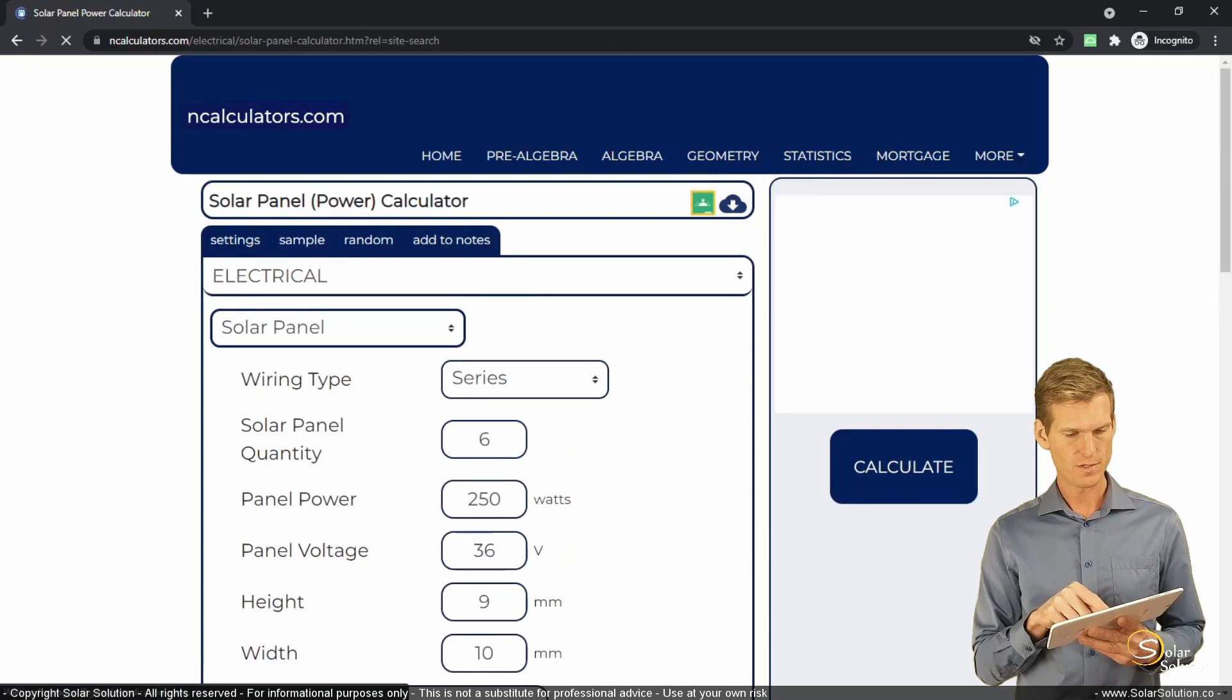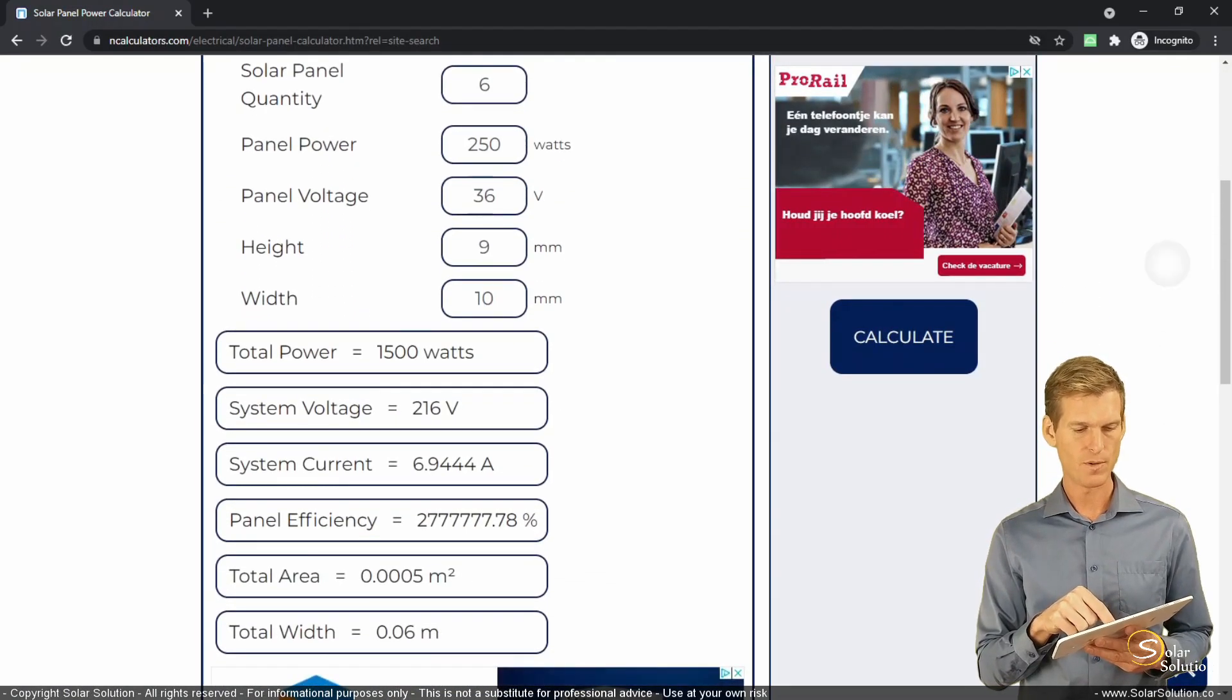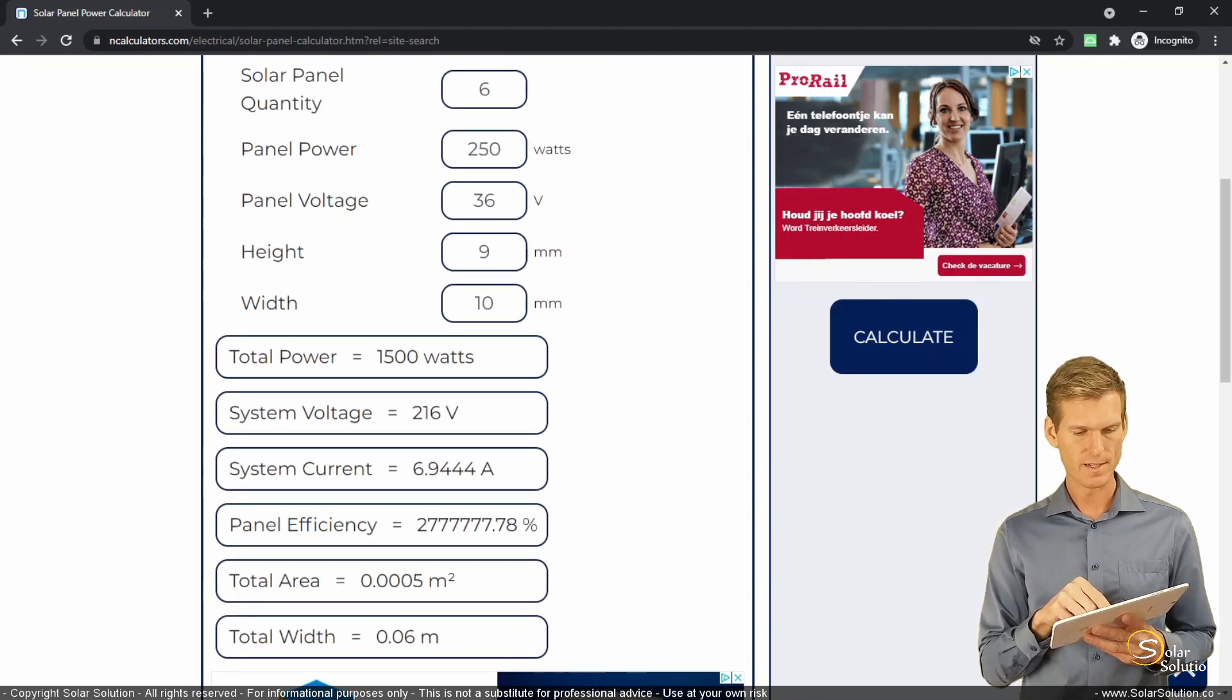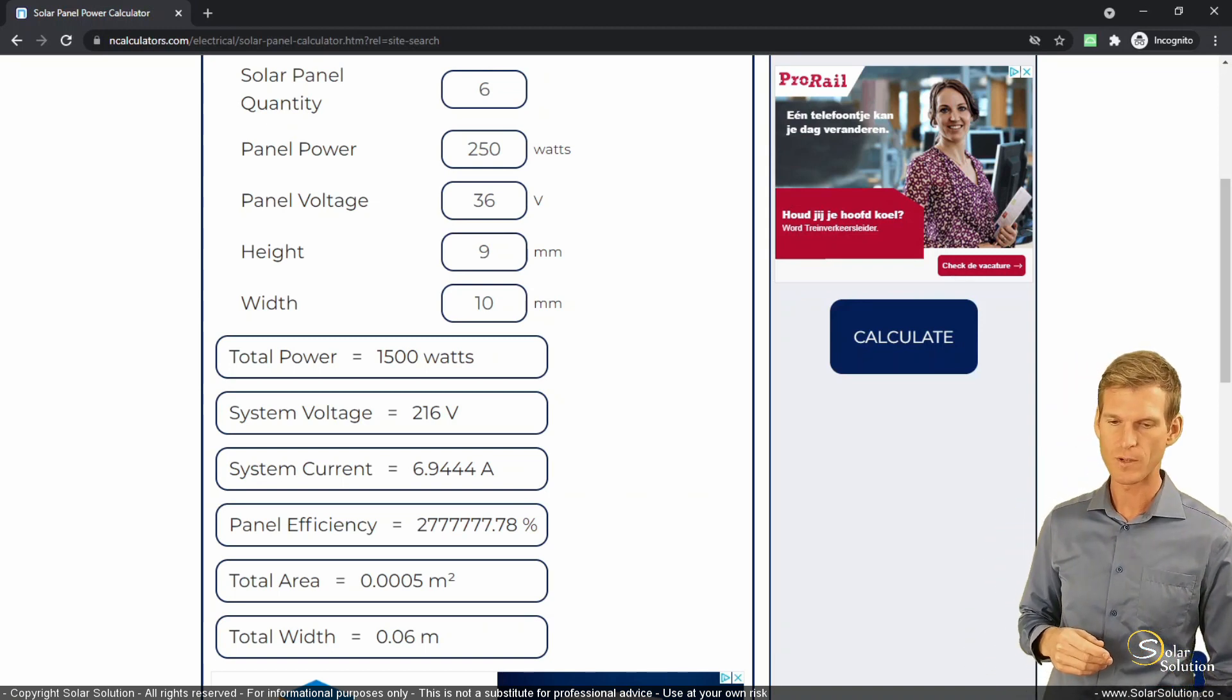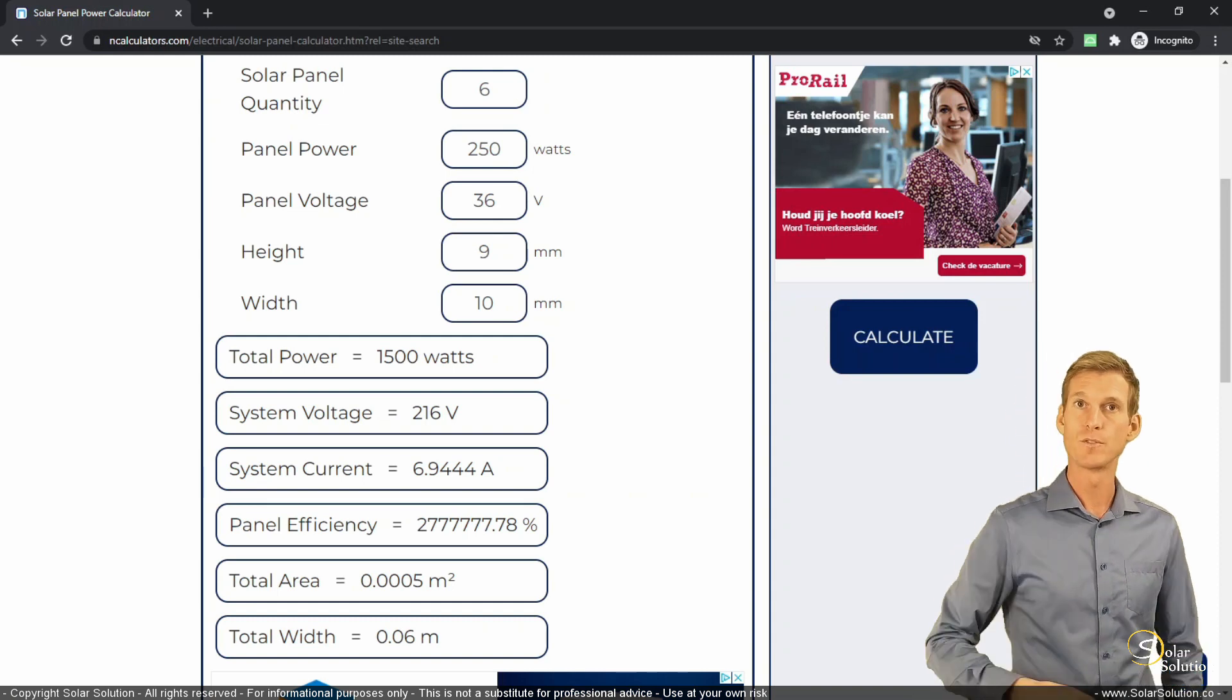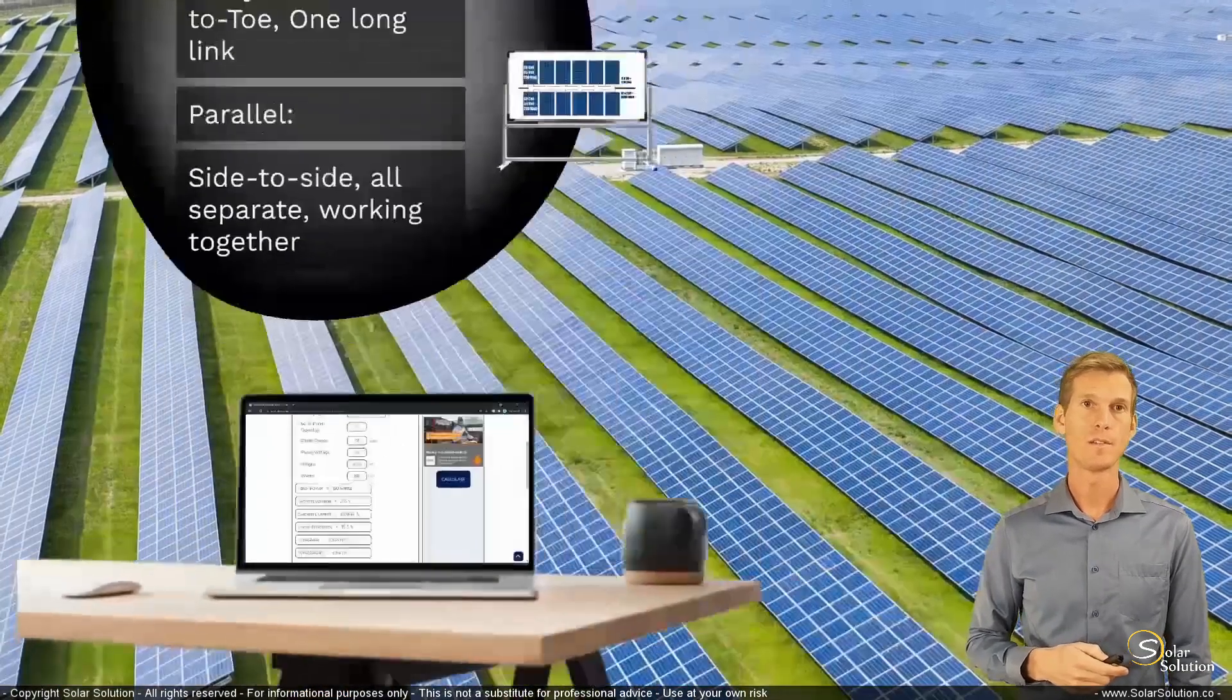And there you go. So six of these panels wired in series produce a total power output of 1,500 watts and a total theoretical open circuit voltage of 216 volts. So there you go. That's just an example of one of the calculators that you can find online. Again, it's just if you feel lazy, of course you can also use a regular calculator. So this concludes the subchapter on the series.